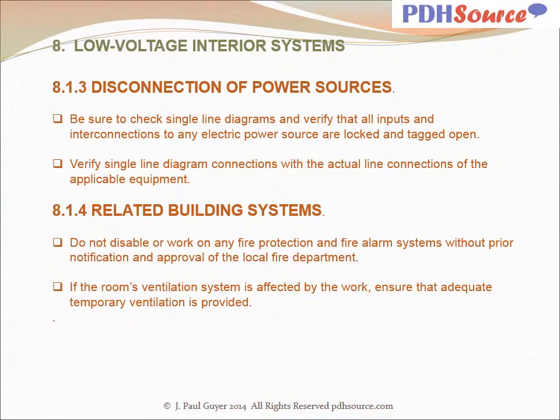Be sure to check single-line diagrams and verify that all inputs and interconnections to any electric power source are locked and tagged open. Verify single-line diagram connections with the actual line connections of the applicable equipment. Do not disable or work on any fire protection and fire alarm systems without prior notification and approval of the local fire department. If the room's ventilation system is affected by the work, ensure that adequate temporary ventilation is provided.